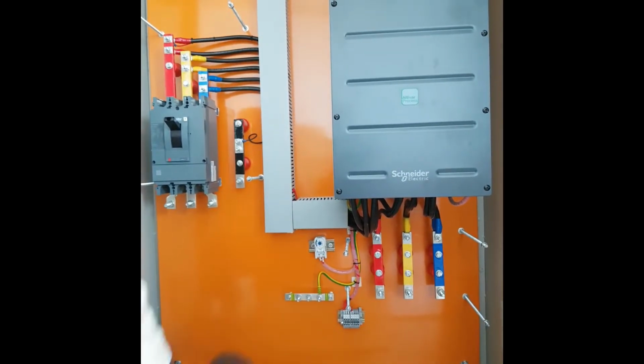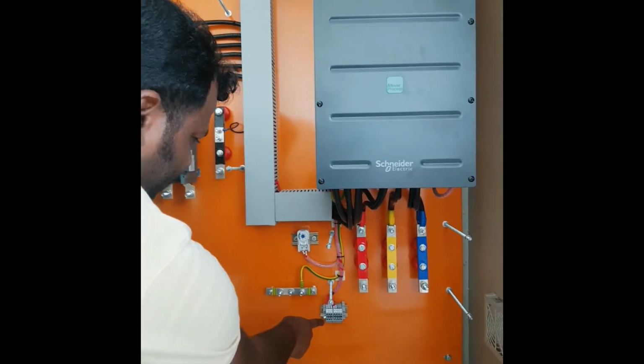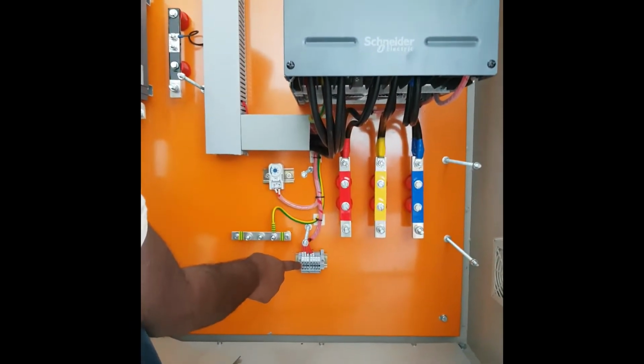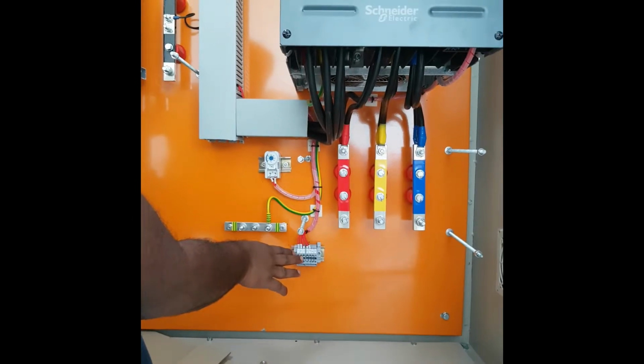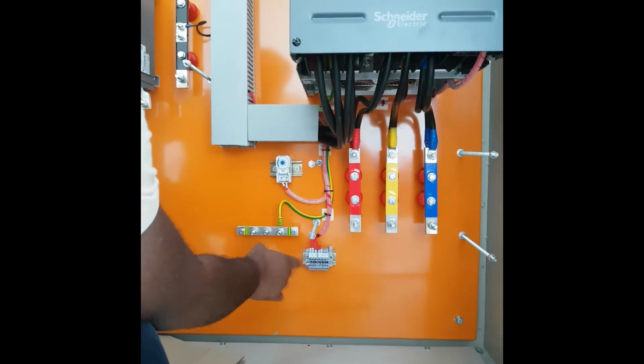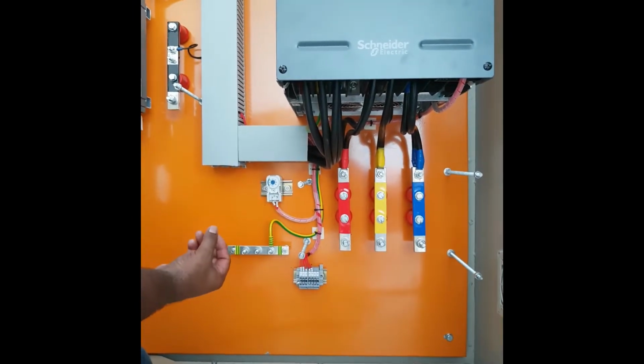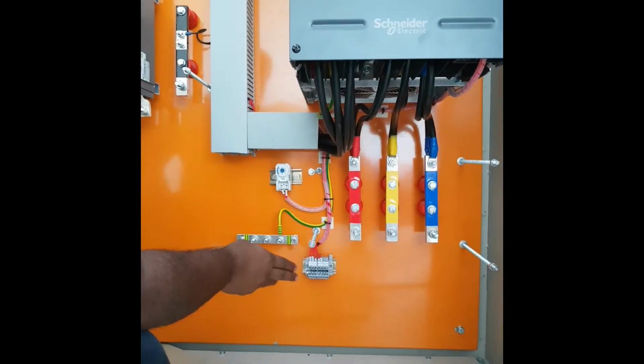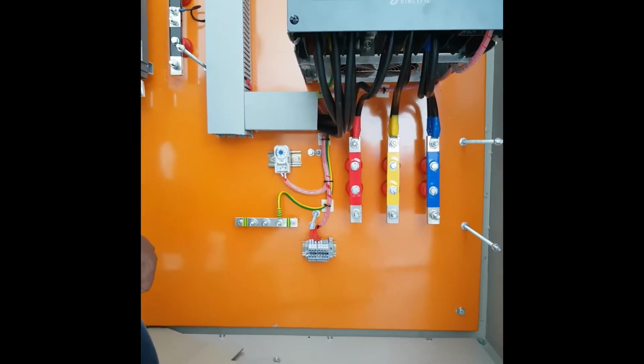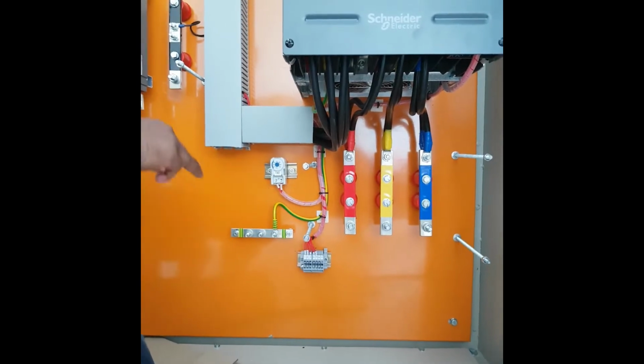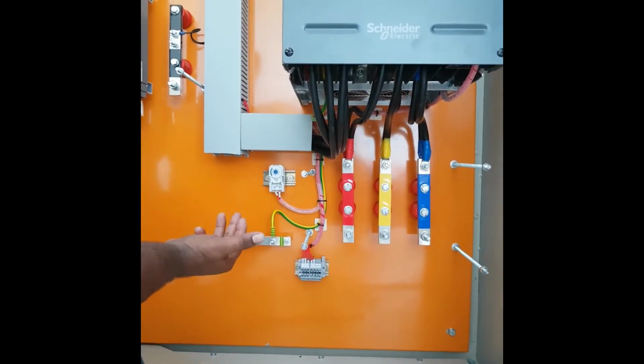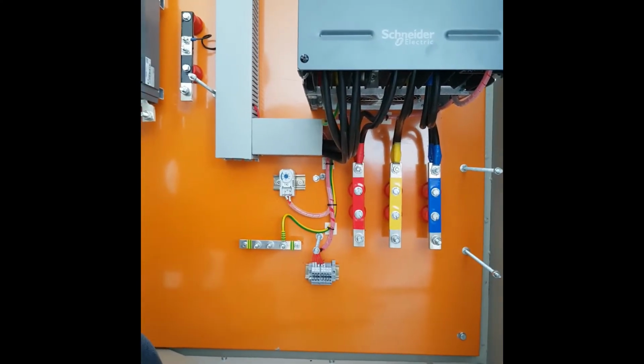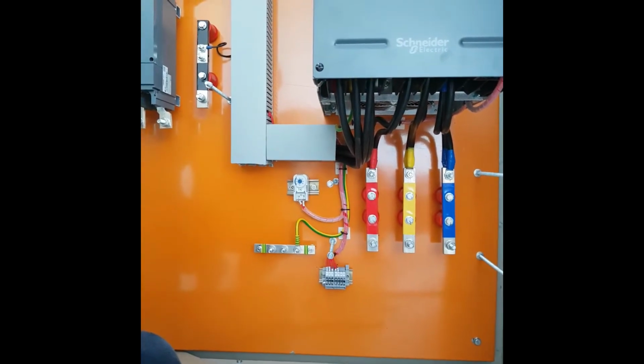Okay, and we have given some control terminals. There are 5 wires connected in the control terminal. The first 3 terminals, as I told you, are for dry run protection. Through these terminals level sensors will be connected, so that the level sensor will sense the water level and give a signal to the level relay. So the level relay will monitor the water level and act.